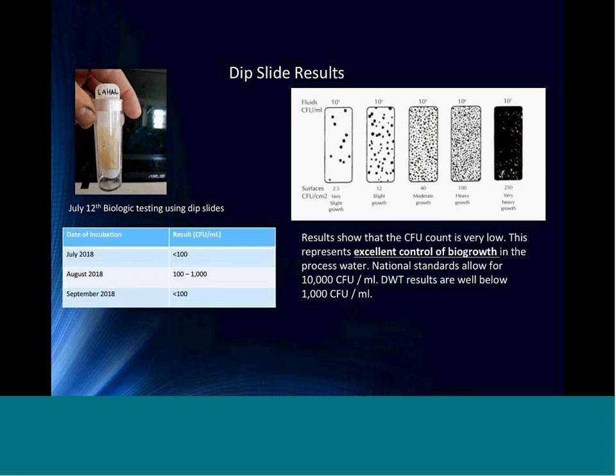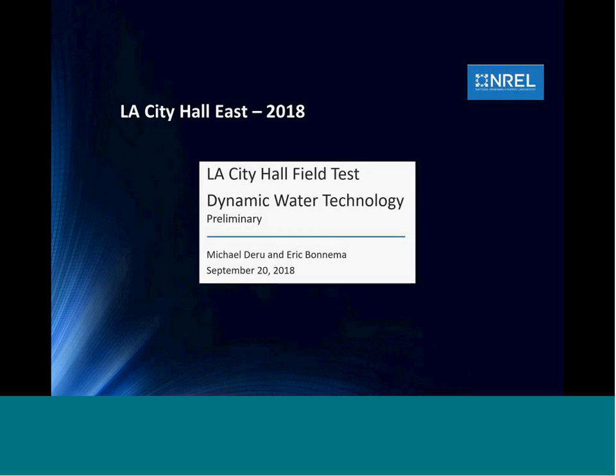We're also actively checking dip slides, and so we're monitoring any kind of biologic growth. We've had excellent biologic results from the process. You can have up to 10,000 colony forming units per milliliter in most cooling towers in the United States, although New York State has actually changed to 1,000. Our processes are typically well under 100 and always under 1,000 CFU. This is just a little reference if you're not familiar with dip slide results, but we'd like to do this once a month just to double check. Next slide, please.